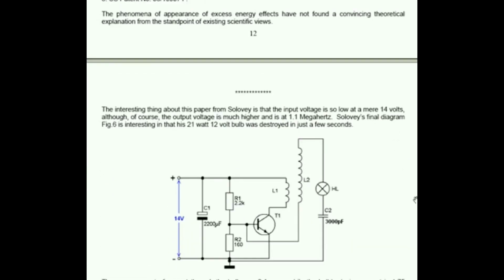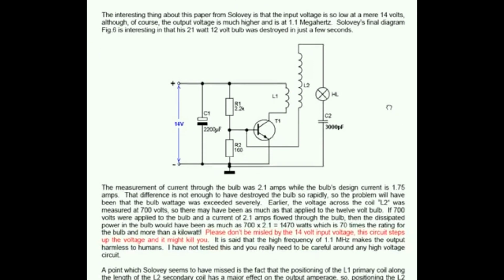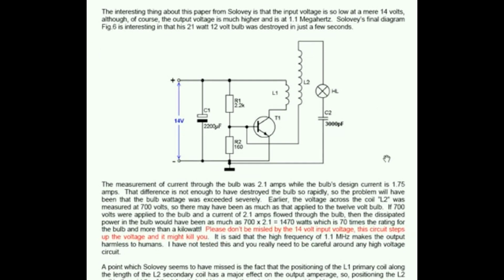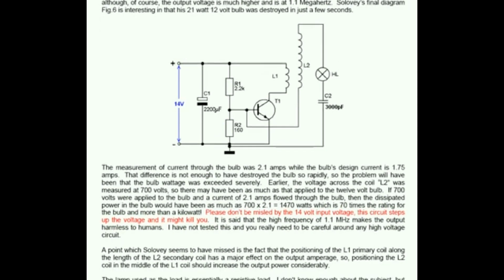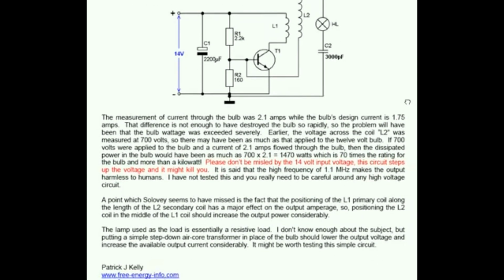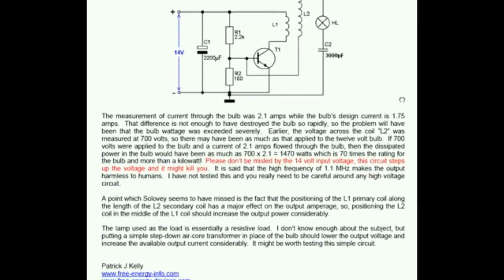Earlier, the voltage across the L2 coil was measured at 700 volts, so there may have been as much as 700 volts applied to the 12 volt bulb. If 700 volts were applied to the bulb and a current of 2.1 amps flowed through the bulb, then the dissipated power in the bulb would have been as much as 700 times 2.1, which is 1,470 watts, which is 70 times the rating for the bulb, and it's more than 1 kilowatt.